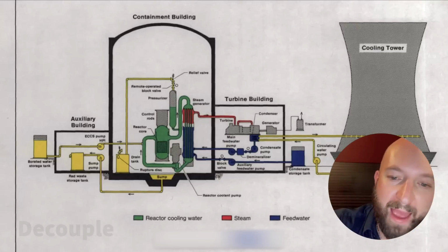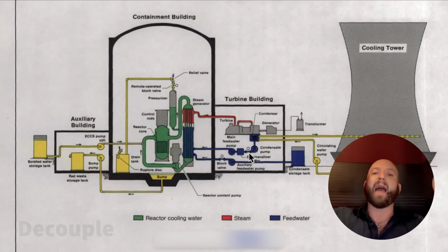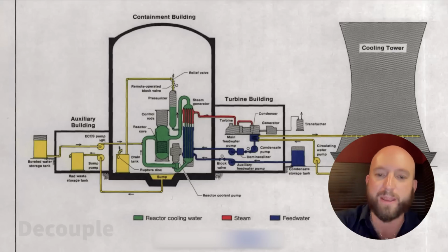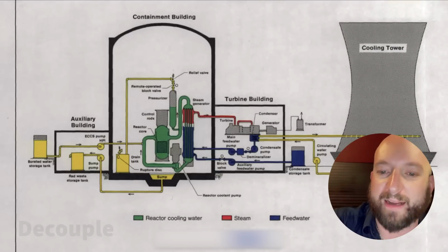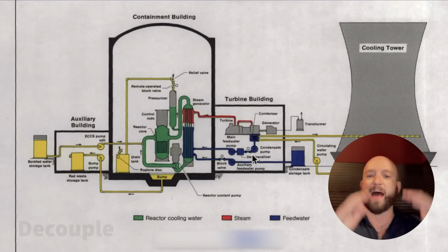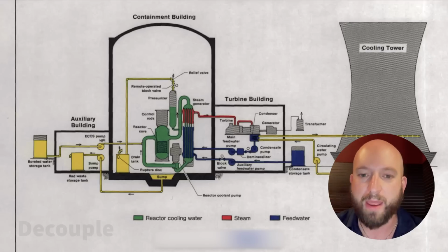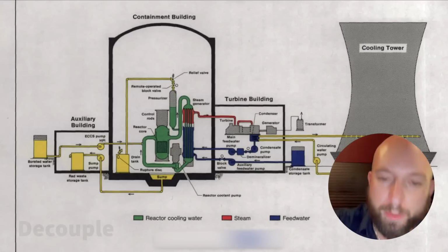Okay, great. So what happens at Three Mile Island? It's 4 a.m. Literally, it's 4 o'clock, 00 and 38 seconds on the clock. So what's the first thing that happens? Operators are doing some work on a high-pressure air system that is used to control the valves in the plant. As a result of that, this valve right here, that's in between the condensate pump and the feed water pump, is accidentally closed, slamming shut the source of water that the condensate pump needs for the feed water pump. That means that the feed water pump shuts down.